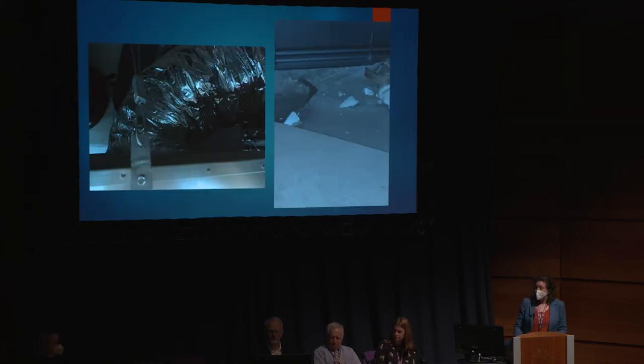When that agar plate raised the alarm, we looked up in the ceiling and found a big tear in the side of the ducting. What was happening is the clean air was coming in but going through the ceiling space, accessing through all the little holes and taking in all the dust. If you've ever been up in a ceiling space - and I've been up in lots - there's always stuff up there you wouldn't believe: bits and pieces, leftover sweet wrappers. That was coming straight in unfiltered, despite beautifully filtered air coming all the way to that point.